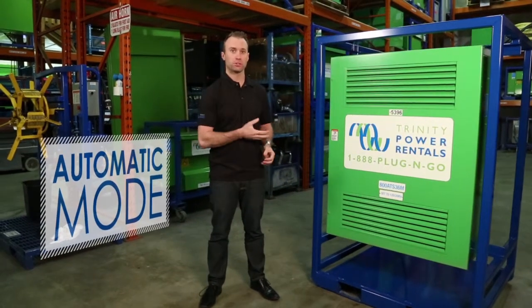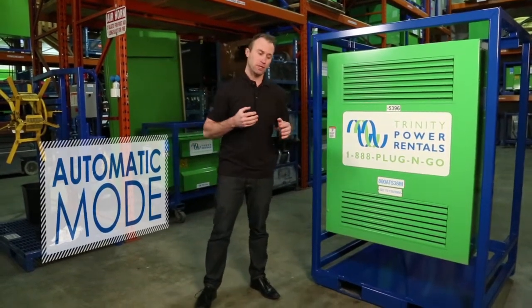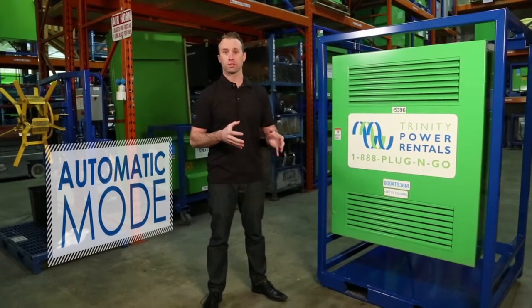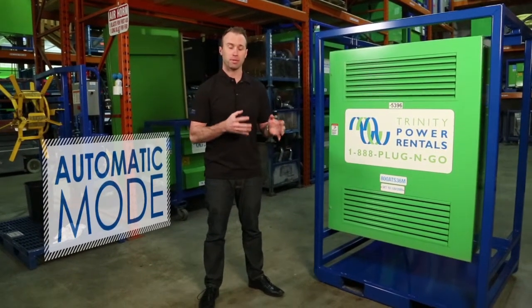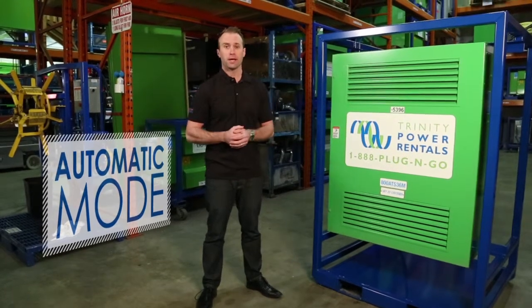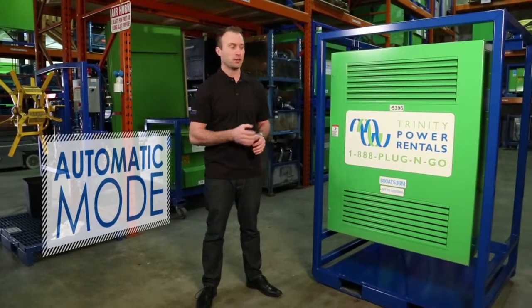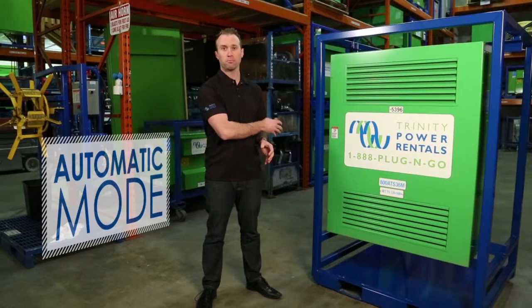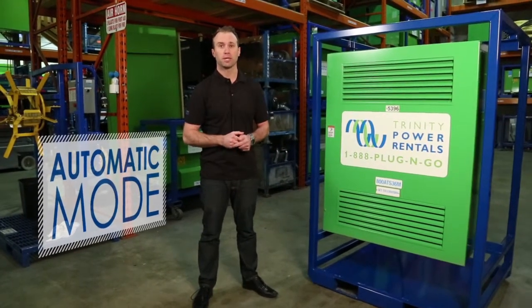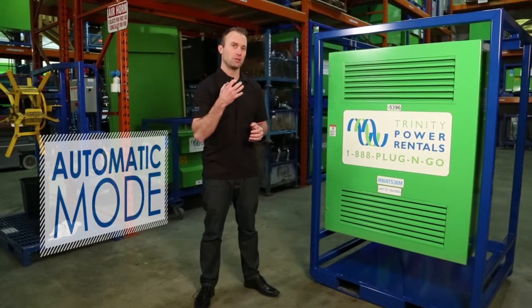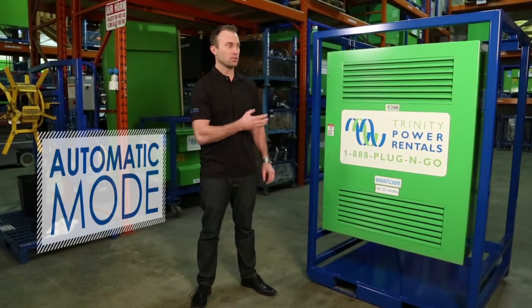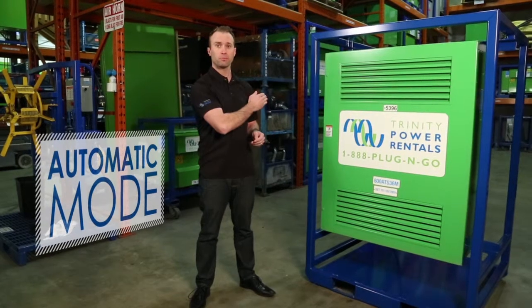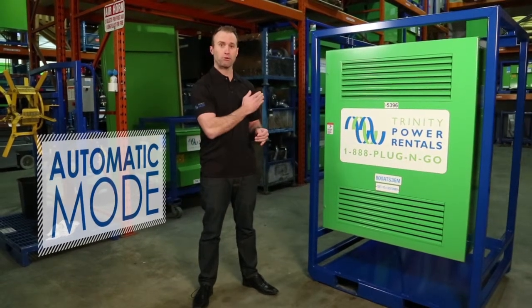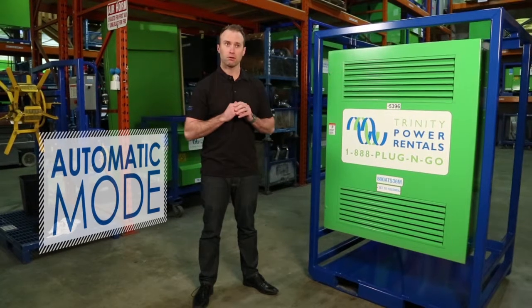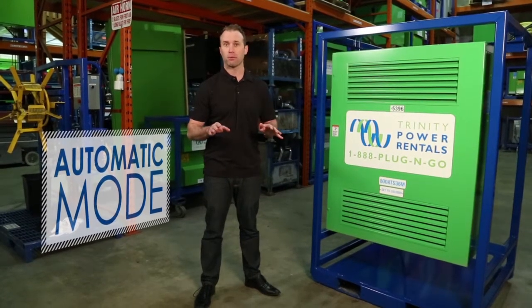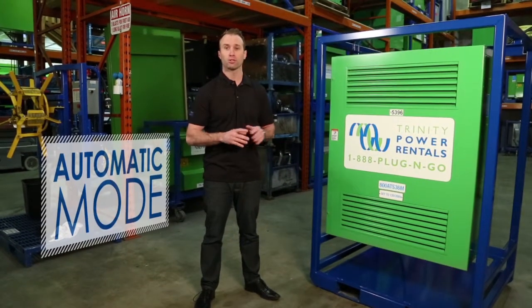A common scenario where this unit would be used in automatic mode is for a high-rise office or residential building, where the transformer supplying that building is showing signs of failure. To ensure minimal downtime, this unit would be paired up with a standby generator and switched to automatic mode. So if the transformer or utility goes down, this unit will automatically start the generator and transfer the load to the generator power source. This happens all automatically, without any manpower on site to monitor it or ensure it's happened properly.